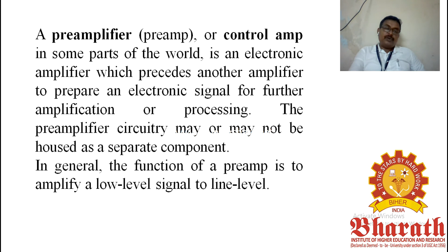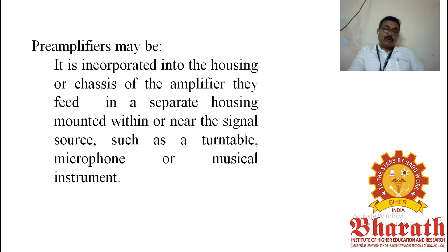So, a pre-amplifier, preamp, or control amp in some parts of the world, is an electronic amplifier which precedes another amplifier to prepare an electronic signal for further amplification or processing. The pre-amplifier circuitry may or may not be housed as a separate component. In general, the function of a preamp is to amplify a low level signal to a line level signal, that is, a usable value. In all medical instruments, of course, the value is going to be very small, so we should go for a pre-amplifier. Pre-amplifiers may be incorporated into the housing or chassis of the amplifier, or fed in a separate housing mounted within or near the signal source, such as a turntable, microphone or a musical instrument, right.